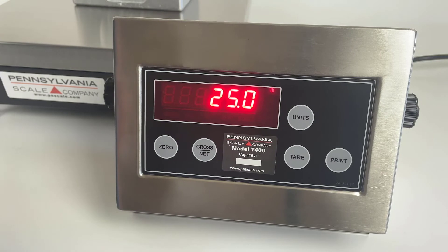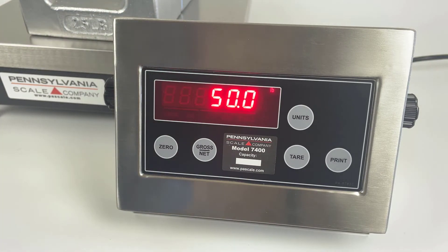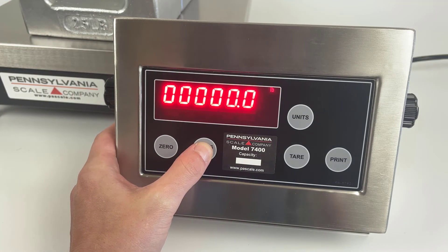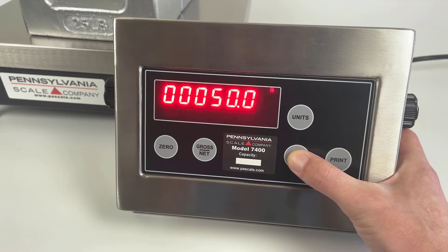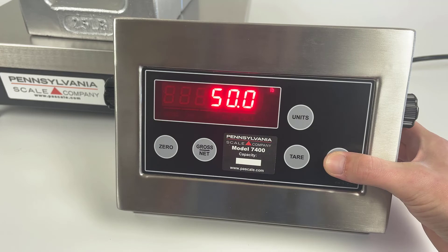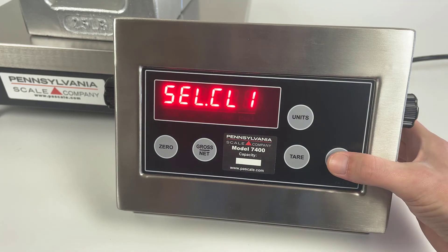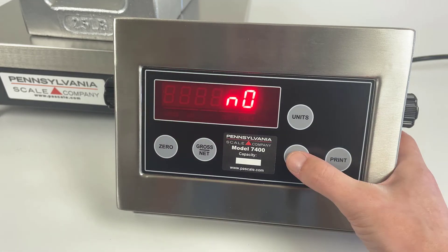Next, you can add more weight to the scale. Again, use the gross/net key and tare key to input the value of the weight you've placed on the scale. Pressing print then calibrates. When you are finished, press the print key to return to the main menu.